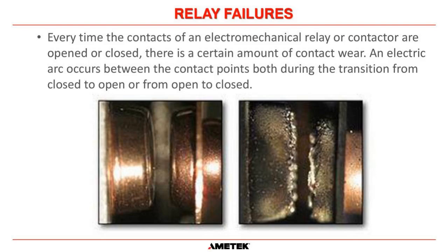It can cause build up on the contact surface, and eventually it's going to cause either a high resistance connection, or it's going to cause a situation where the connection doesn't get made at all. So it's extremely important for critical relays in any system, never mind a UPS, that if it is critical to the operation of your plant, you should be changing your relays on a very frequent basis.